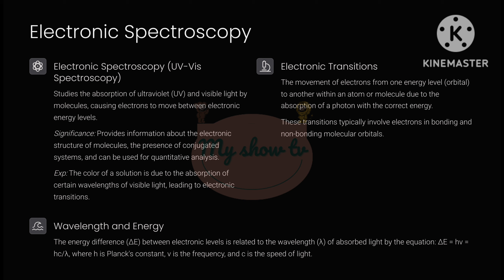To perform electronic spectroscopy, we use an instrument called a UV-vis spectrophotometer. It's designed to shine UV and visible light through a sample and measure how much light is absorbed at different wavelengths. The basic components are 1. Light source. This provides the broad spectrum of UV and visible light needed for the analysis. We typically use two different lamps to cover the entire range: a deuterium lamp for the UV region and a tungsten lamp for the visible region. These lamps emit a continuous range of wavelengths.